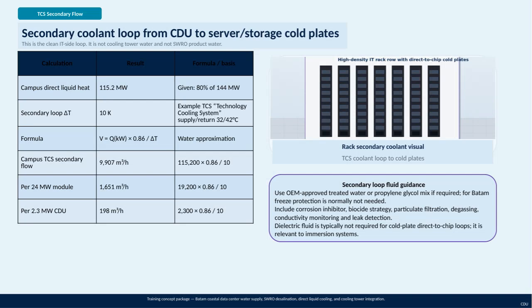Here we have an overview of the TCS secondary flow, which refers to the secondary coolant loop running from the CDU to the server and storage cold plates. It's important to note that this loop is part of the clean IT side cooling system. Unlike other cooling loops, it does not use water from a cooling tower or SWRO desalinated water. This distinction is critical for maintaining system cleanliness and performance. Looking at the technical side, this loop handles about 115.2 megawatts of direct liquid heat in the campus, which is calculated as 80% of the total 144 megawatts.